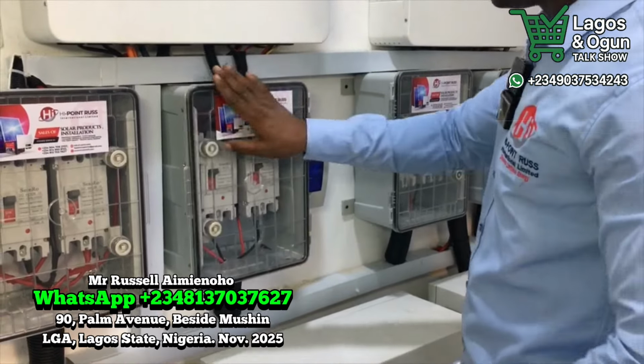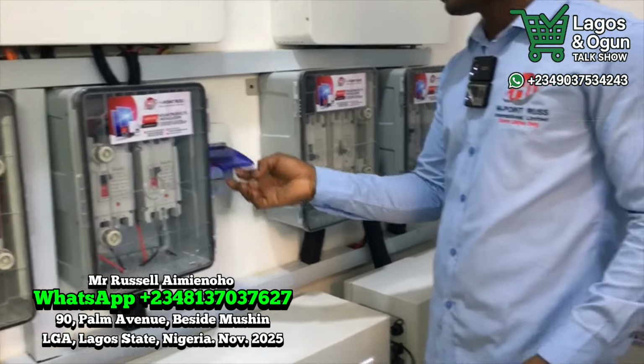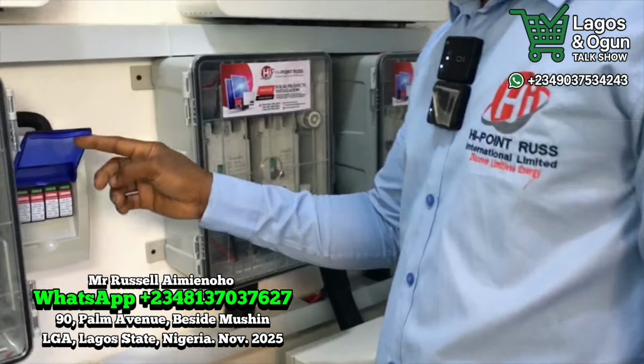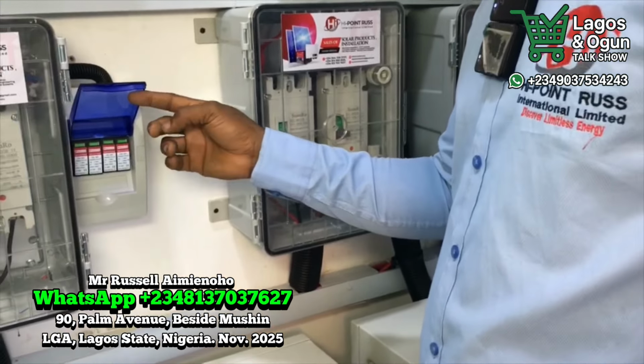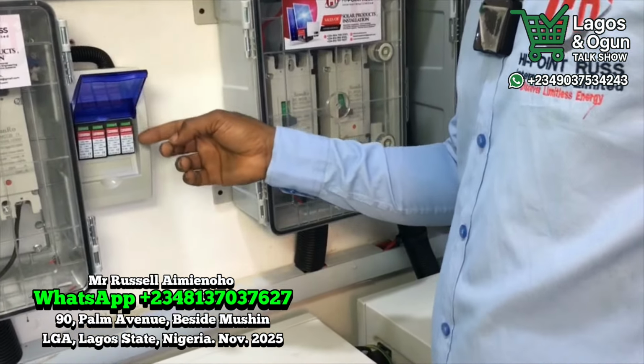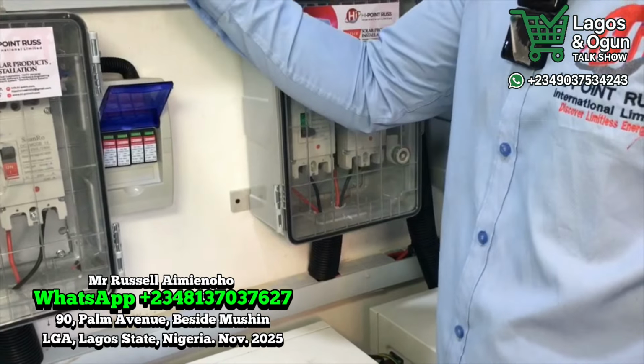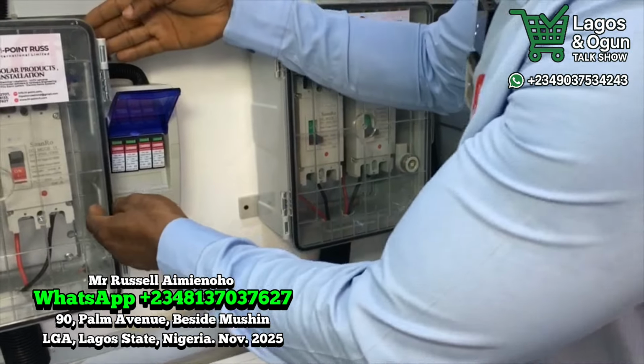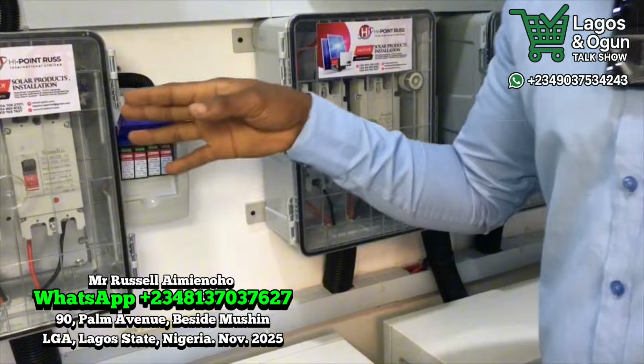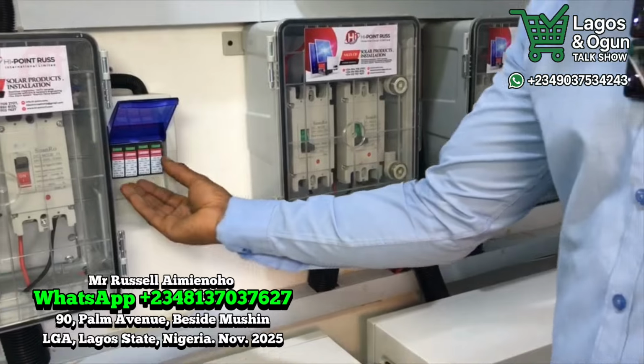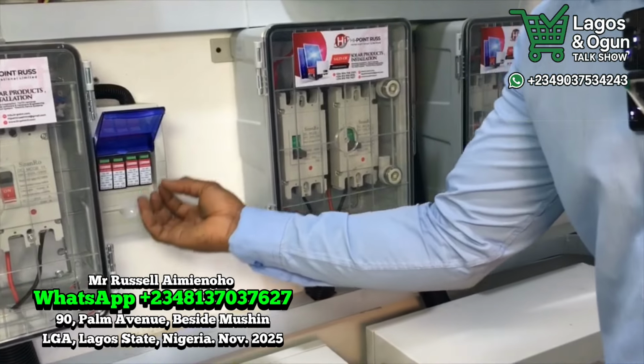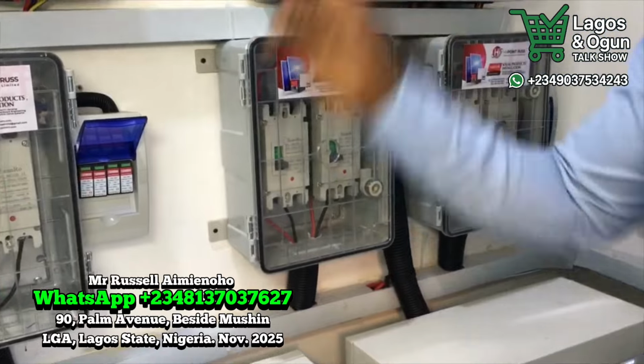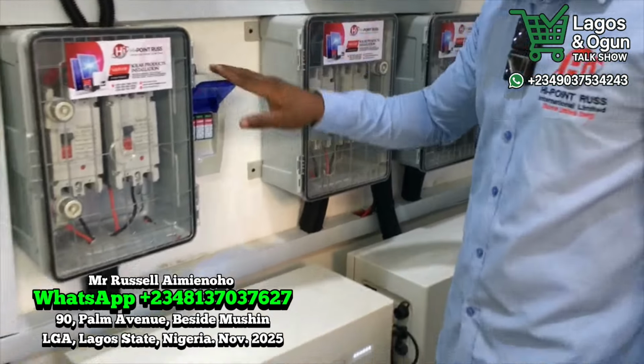Don't stop there yet, bring the camera back because we also have an SPD by the side. This SPD is what we call a surge protecting device, and it protects the system. God forbid a malfunction comes from the PV with high voltage, the SPD will take that excess voltage and pass it through earth, bringing it down to earth so it doesn't affect the system.